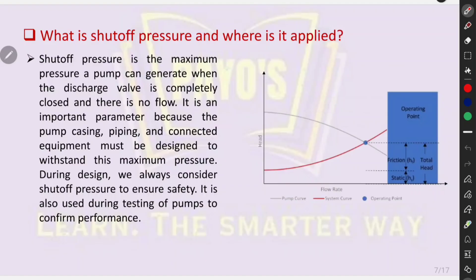What is shutoff pressure and where is it applied? Shutoff pressure is the maximum pressure a pump can generate when the discharge valve is completely closed and there is no flow. It is an important parameter because the pump casing, piping, and connected equipment must be designed to withstand this maximum pressure. During design, we always consider shutoff pressure to ensure safety. It is also used during testing of pumps to confirm performance.